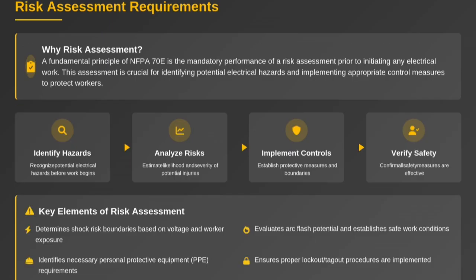NFPA 70E requires a risk assessment before any electrical work begins. This means identifying hazards, analyzing the risks, implementing control measures, and verifying safety before starting the task. A proper assessment determines boundaries for shock risk, specifies PPE requirements, ensures Lockout/Tagout is in place, and evaluates the potential for arc flash. In short, risk assessment is the foundation of safe electrical work.